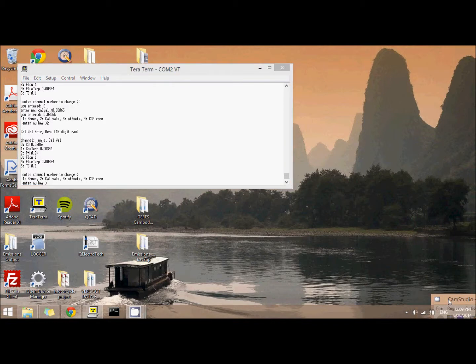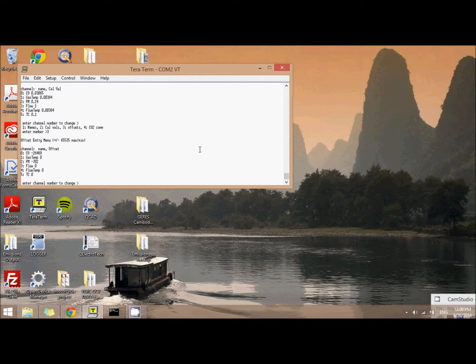So now I'm going to enter that offset and go into menu option 3. There I see it, the offset menu. And it's set up similar to the CalVal menu. I see my current carbon monoxide offset at -26469. This will be different for your sensor box, but it should look something like that. But you'll notice that usually the offset you've calculated during your calibration procedure is much smaller. So for instance, on this calibration, I got a value of -31. And all I have to do is, instead of changing the CO to -31, I just want to subtract that from my current CO value. So instead of entering -31 in this spot, I'm going to subtract that from our current calibration value.